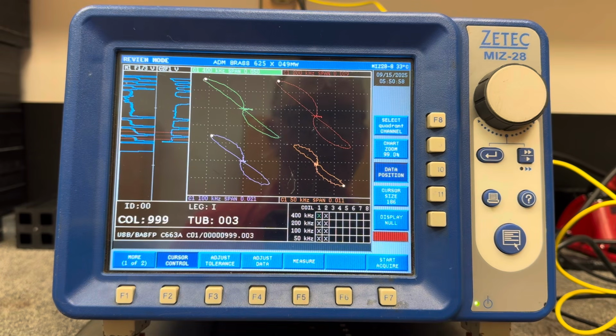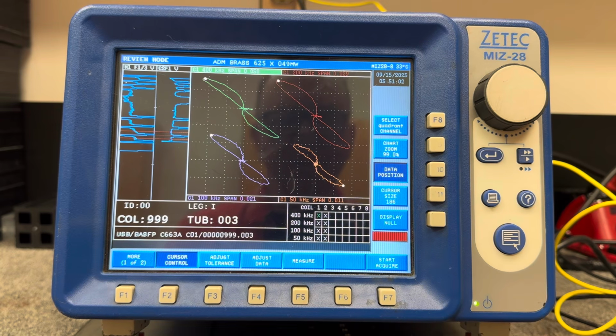This tester is a Zetec Miz-28. Currently set up for doing bobbin testing, but you can do bobbin or surface testing. So testing tubes, testing surface, you can do it all. It's multi-frequency, capable of operating in the differential and absolute mode, which means you can perform mixes and mix out those pesky support plates. So what I'm using today, just have a setup, the CoreStar bobbin probe.